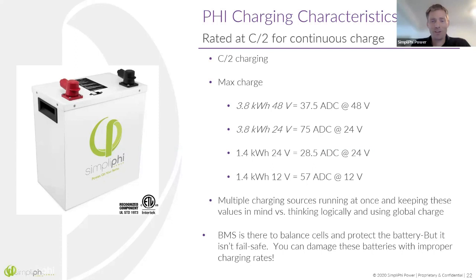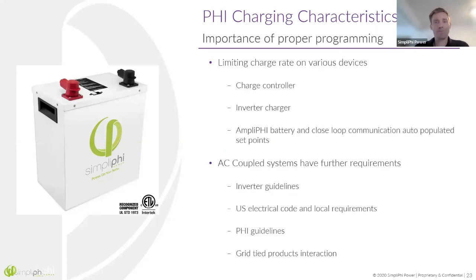So this came up as a question earlier. The BMS is there to balance the cells and protect the battery. There are fuses on these batteries, but you can still damage the batteries with improper charging rates. So be careful. Use the settings that are recommended. So you want to make sure to limit charge rate on your charge controller. And if you've got an inverter charging the batteries from AC, you want to make sure that you're limiting that charging rate to 37.5 amps per battery.